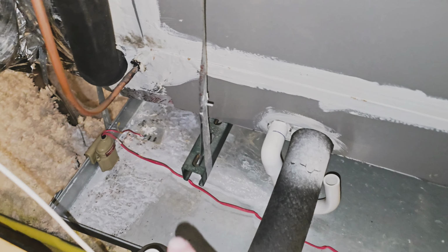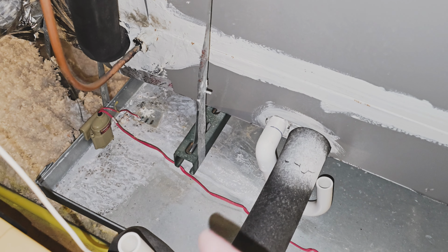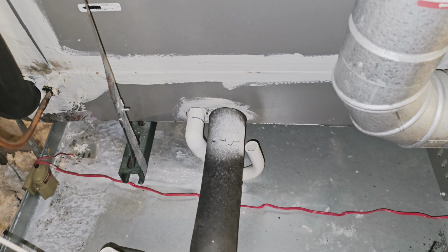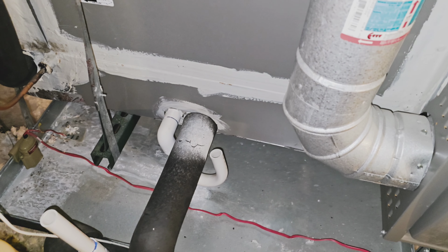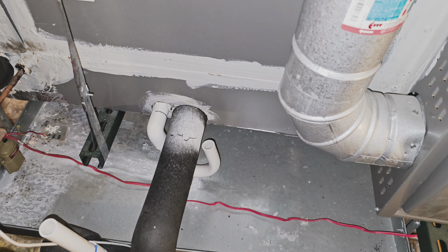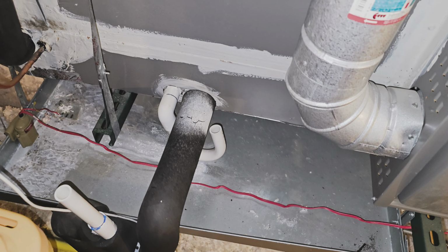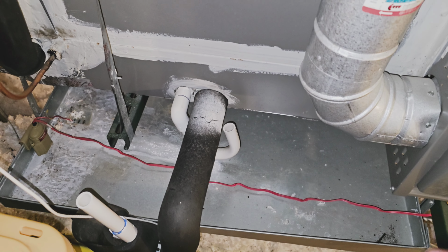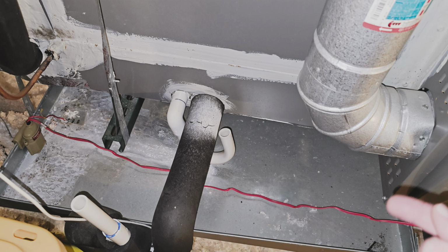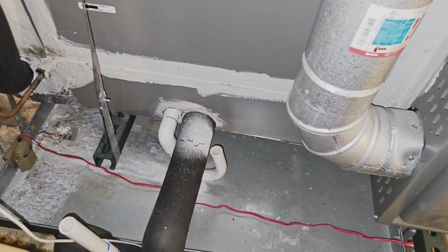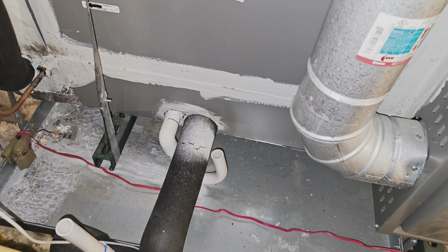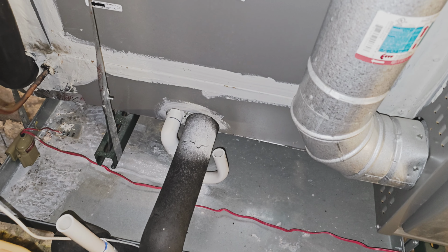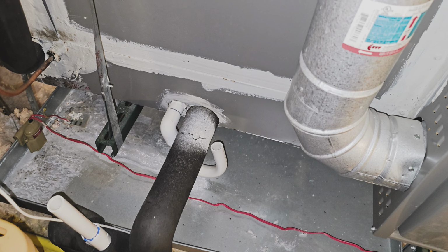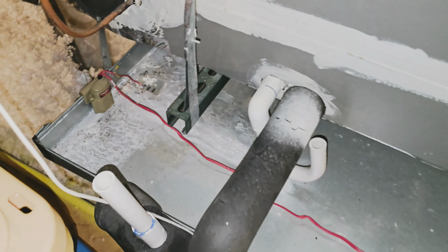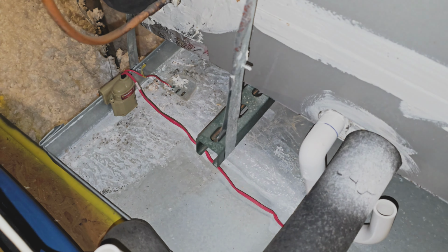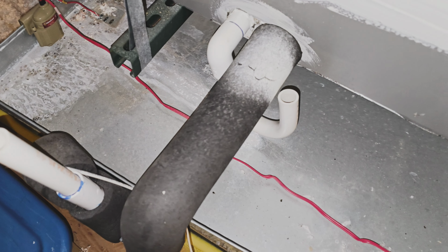I don't need it here because I already got that sensor that's going to shut off my air conditioner if it starts detecting water. But this is the drip pan underneath the air handler for the air conditioner. There should never be any water in this. Basically, you would get a bunch of condensation buildup that's not draining out the drain because you got a clog, and then it'll start flowing into this drip pan. You don't want that, because if the drip pan starts getting full of water, it'll leak onto your ceiling and then you got a water damage problem. But if you got a water leak detector, you can see when this kind of happens and be able to stop it. I already have a sensor that would shut off the air conditioner if it started to detect water, so I'm good there.